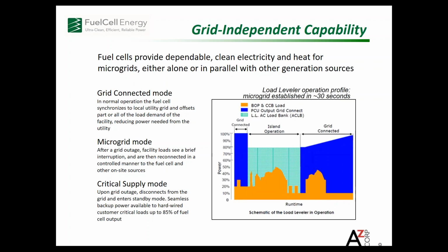The second mode that we've been able to introduce is what we refer to as a microgrid mode. In this mode, we employ what we call a load leveler, so that the power that is generated by the fuel cell that is not required by the facility when the grid is not present is consumed in the load leveler. Naturally, you want to minimize that consumption in the load leveler, but it does allow us to serve transient loads on the facility side because our fuel cell is a base load resource. It really runs flat out 24/7. So naturally, what we would do in the sense of a grid interruption, in this case in our microgrid mode, is we're running the fuel cell, we're matching what the facility needs, and if on a steady state basis, absent the grid, you are below the rated output of the fuel cell, we will gradually ramp down the fuel cell so that we're not wasting fuel.